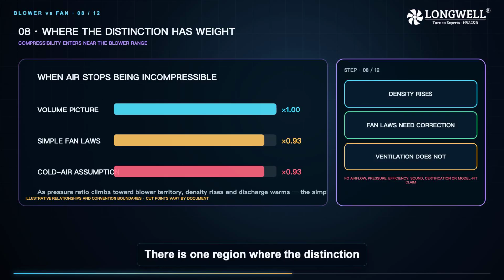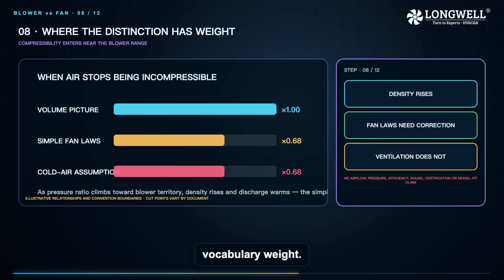There is one region where the distinction carries engineering weight rather than vocabulary weight. As pressure ratio climbs toward the blower range, air stops behaving as if it were incompressible. Density rises through the machine, the discharge air warms noticeably, and the simple fan laws this series uses start needing correction terms. High-pressure blowers are sized with compressibility in mind, ventilation fans are not, and do not need to be.